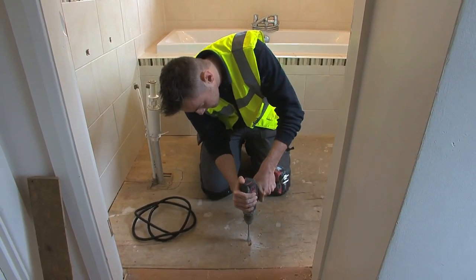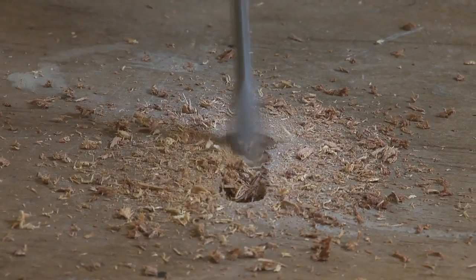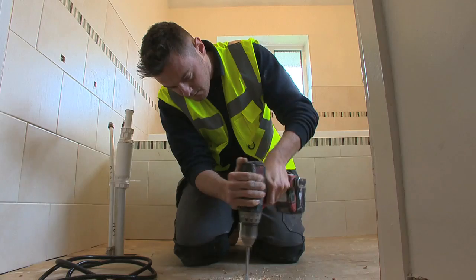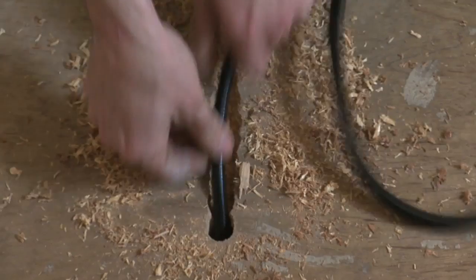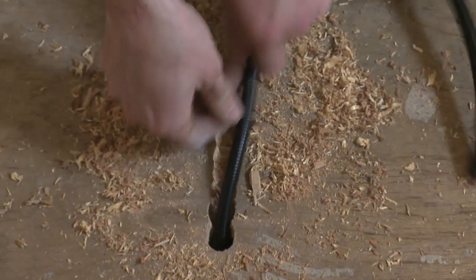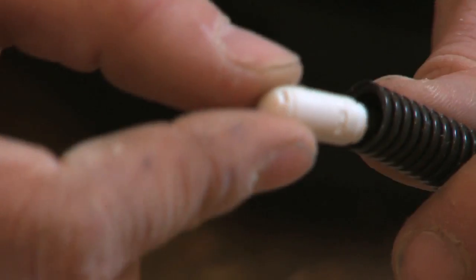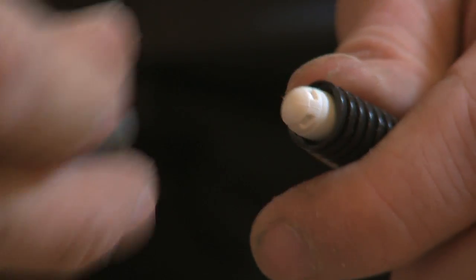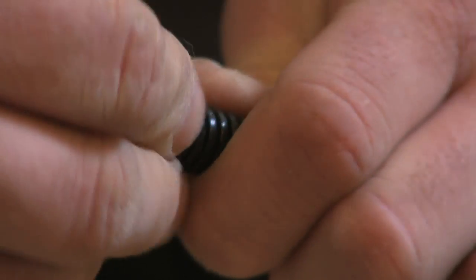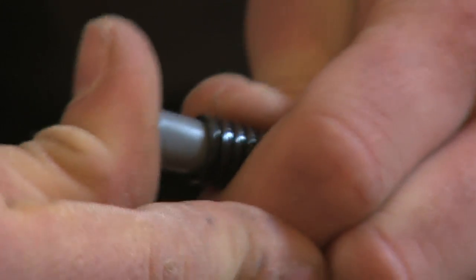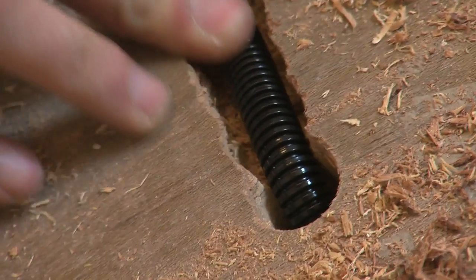Next, cut a groove into the floor for the floor sensor pipe. This will make sure that your floor is always the temperature that you want. The groove should be around 20mm deep. Feed the floor sensor through the flexible pipe as shown here, and then cap the end of the pipe. The sensor must always remain in the flexible pipe. The pipe needs to be accessible at all times in case a floor sensor needs replacing in the future.